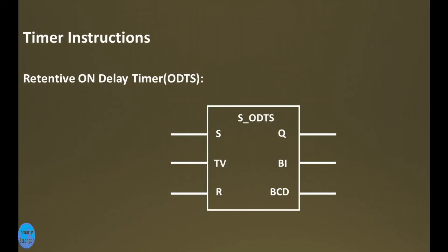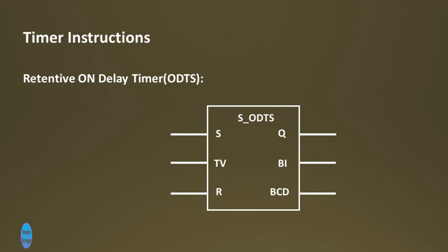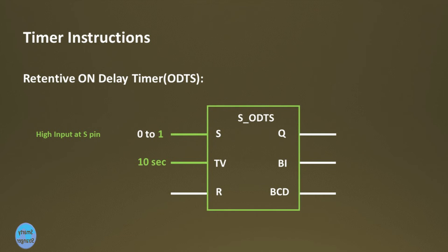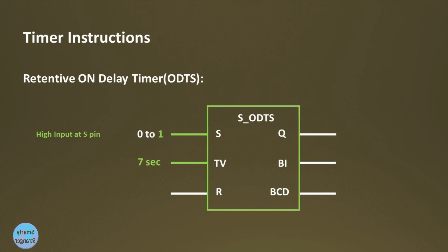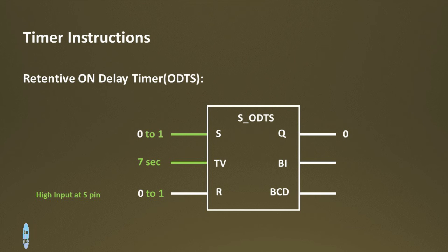If you want a timer which completes its timing, then the Retentive On Delay timer is best suited for you. The Retentive On Delay timer starts the specified timing if there is a positive edge at the S pin. The timer completes its timing and the output will be high. The timer will be re-triggered with the specified time if there is a fluctuation in signal state at S input. The timer is reset only if the reset R input changes from 0 to 1.